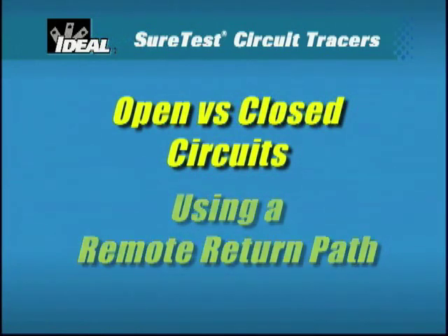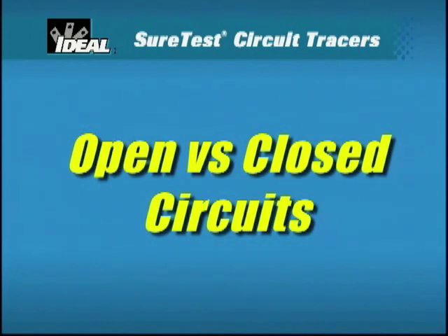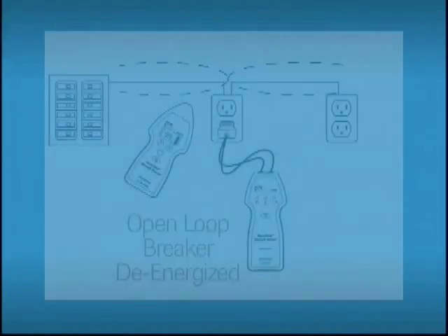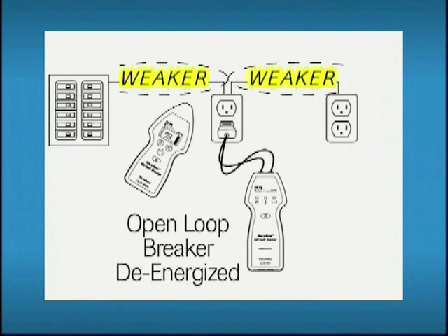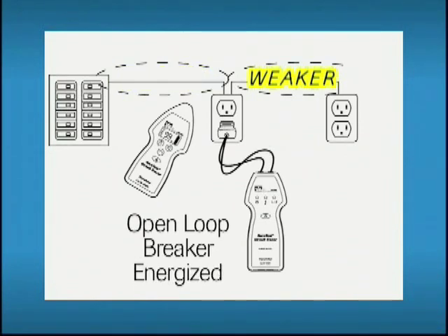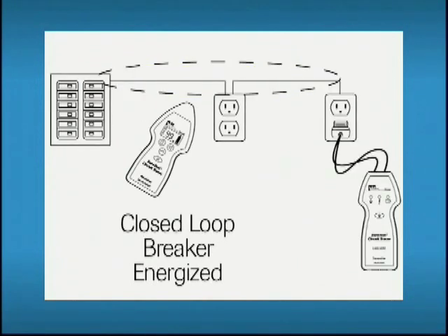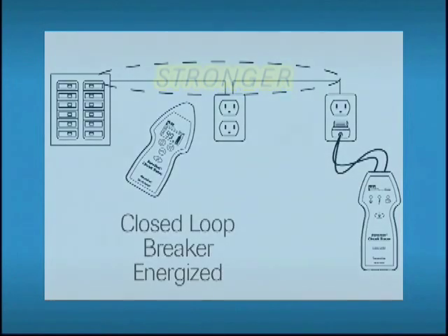The first concept is the effect that an open versus a closed circuit has on the signal. Whether a circuit is open or closed greatly affects the strength of the electromagnetic field. In an open circuit, there is no current flow, so the strength of the magnetic field produced is much weaker. But in an energized closed circuit, current flows to produce a much stronger electromagnetic field, allowing the receiver to detect the signal from a much greater distance. So when possible, set up a closed circuit for tracing.